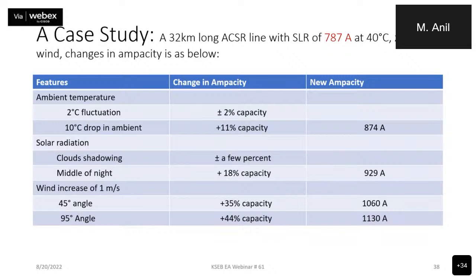That is 787 plus 330 or 340 amperes of enhanced capacity, which can be achieved with the same infrastructure with a wind speed of 1 meter per second at a 95-degree angle. So that is the advantage of using DLR. It's quite advantageous, but for DLR we need to have supporting infrastructure, hardware requirements at the field.